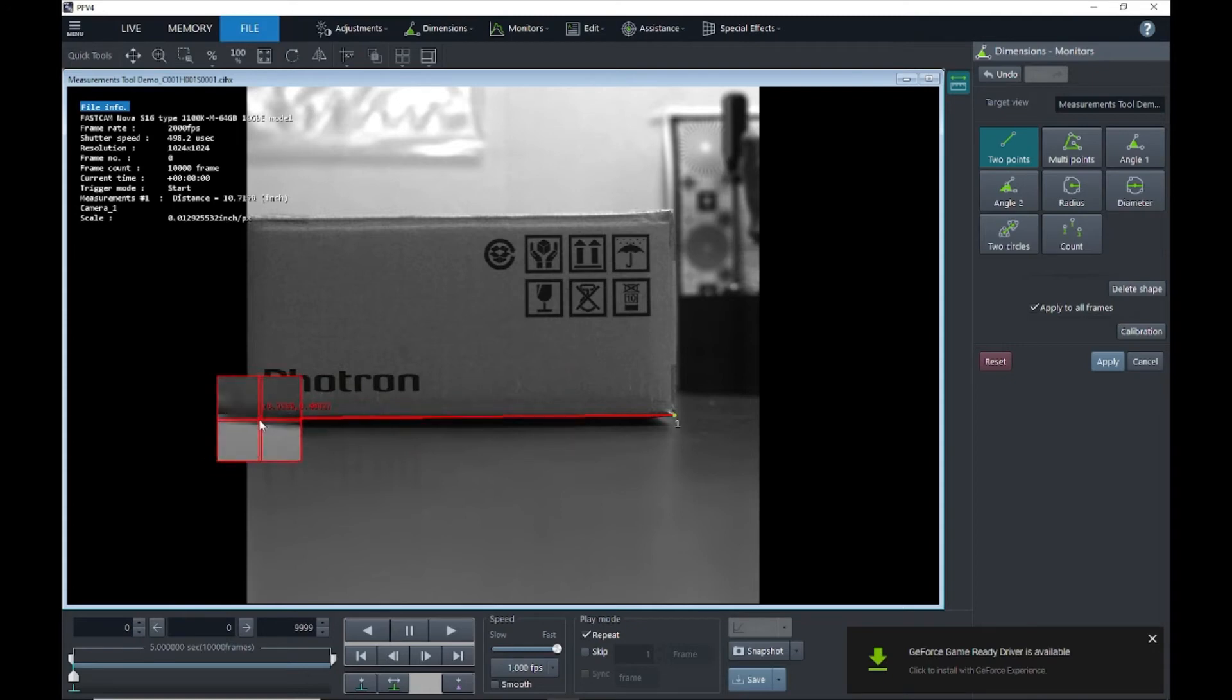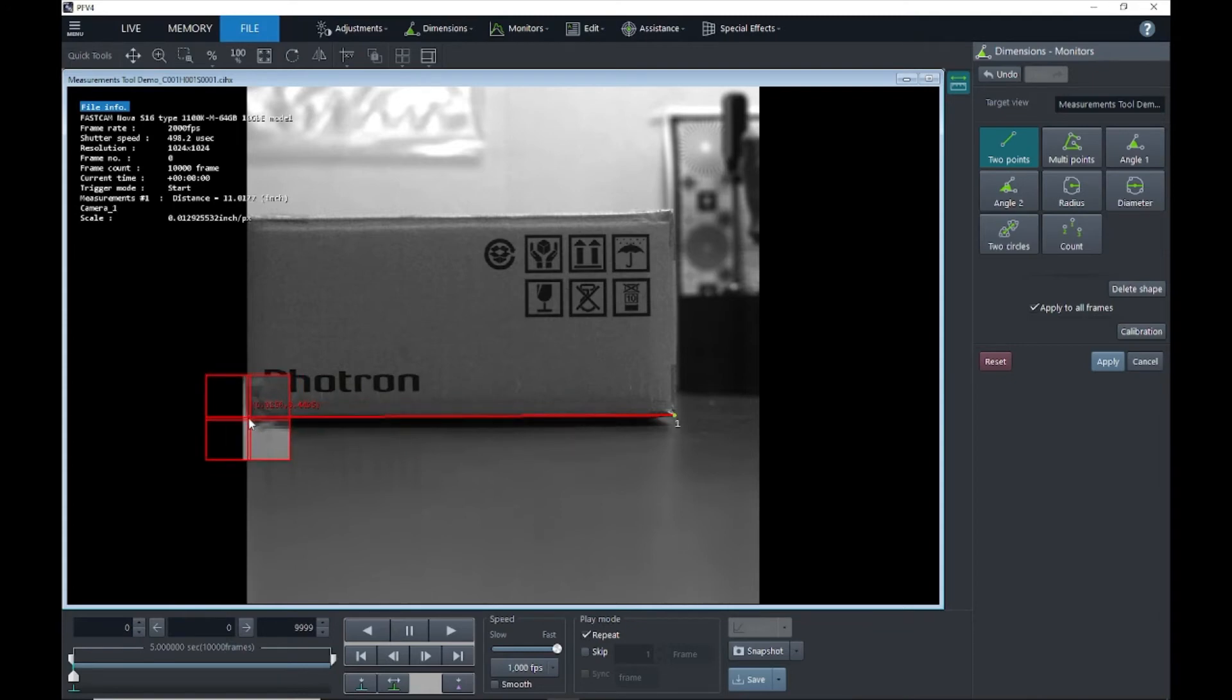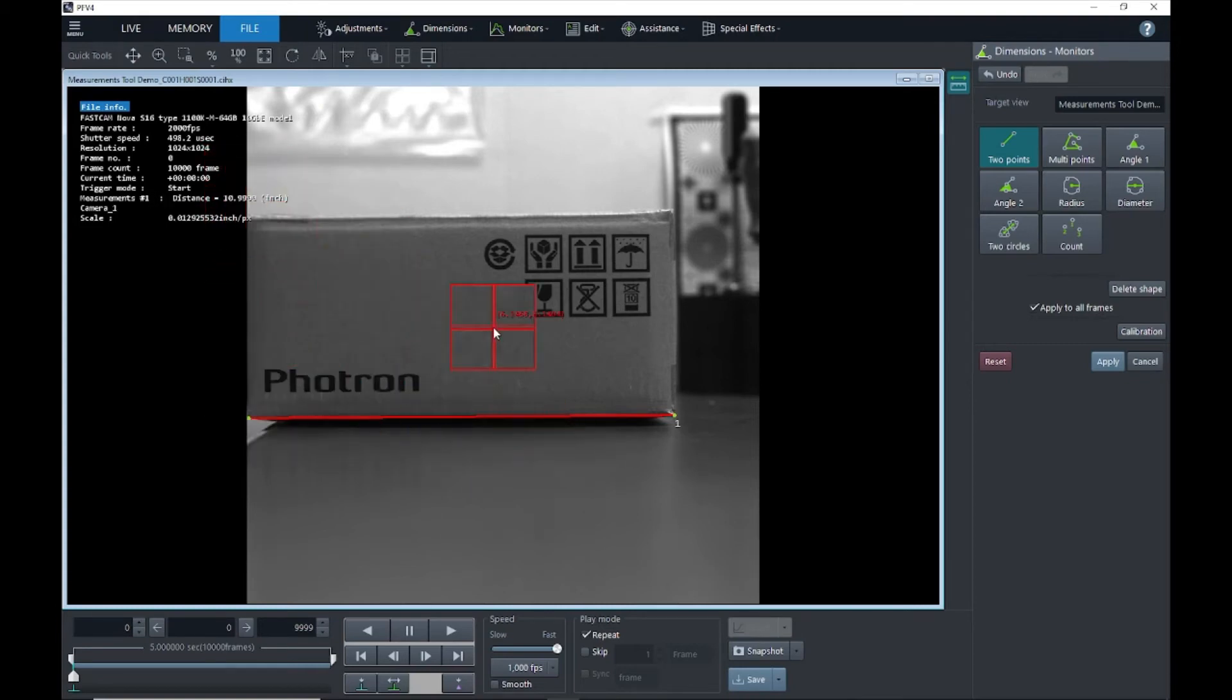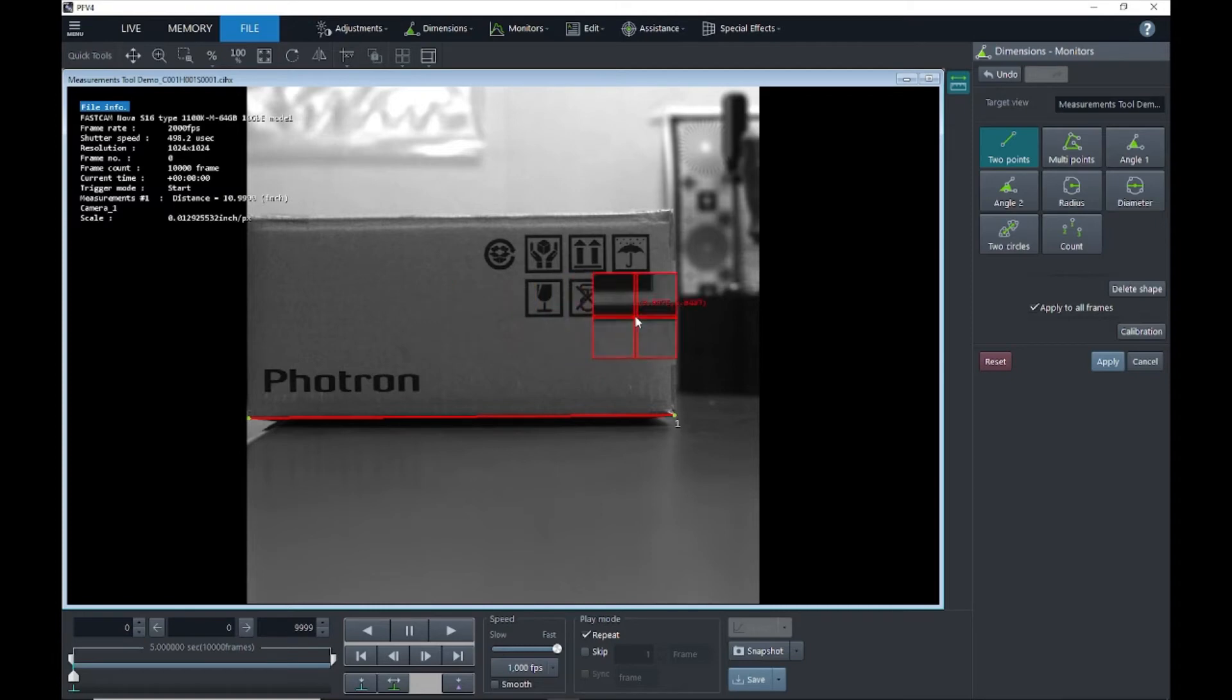So we'll test our box calibration. This should be about 11 inches. We'll go ahead and put on both corners and you'll see right here measurement number one pops up as 10.999 inches. So it looks like our calibration is good.